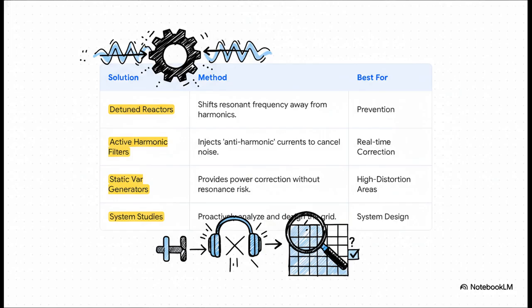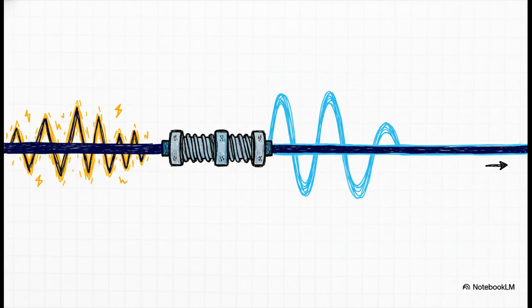And in really high-tech or electrically dirty places, they use things like static VAR generators, which clean up the power without adding any new parts that could cause resonance themselves. Of course, the best tool of all is doing system studies before building anything, to design a resonance-free grid from the start.